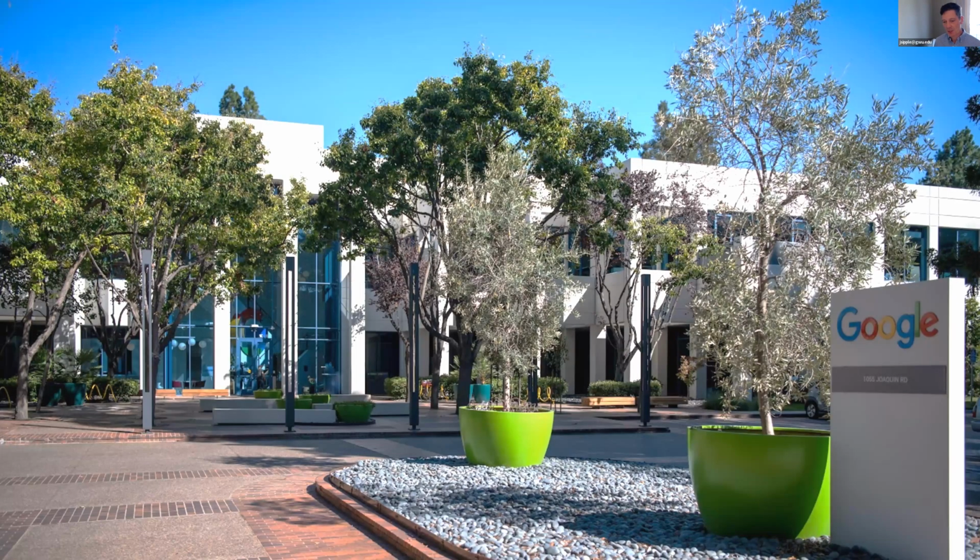But before I go there, this is our test building here, 68,000 square feet, 137 devices. It was somewhere around 512 zones. So it's a fairly representative building, by no means our largest or most modern, but the HVAC system here is fairly well tuned by the technicians. So we wouldn't say this is a very modern building, but we would say it's pretty well maintained. So it's running at a pretty high standard, and achieving the 5% objective is not necessarily going to be an easy task.